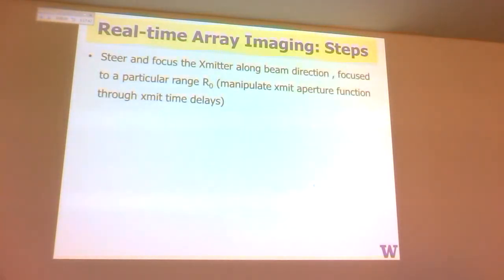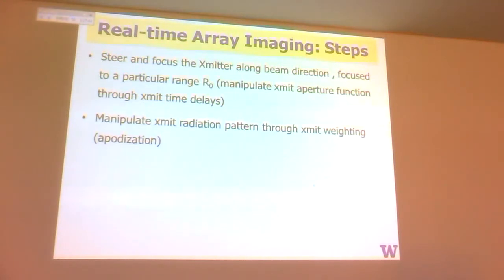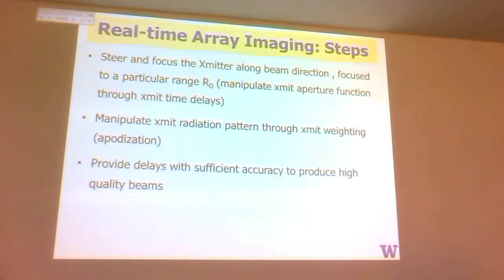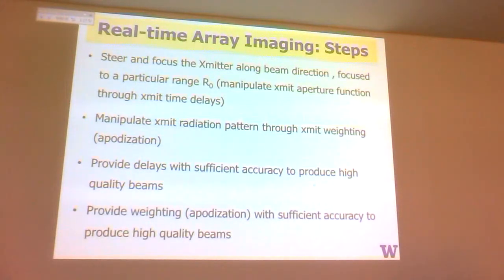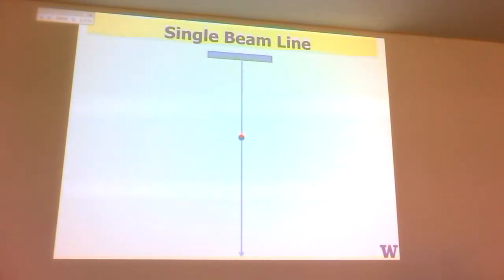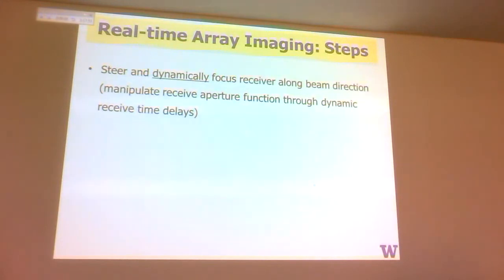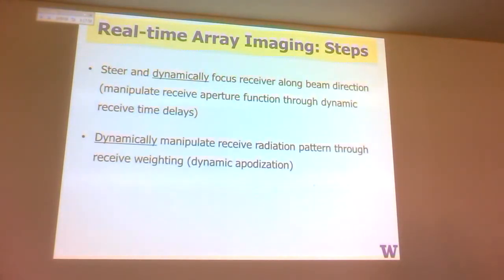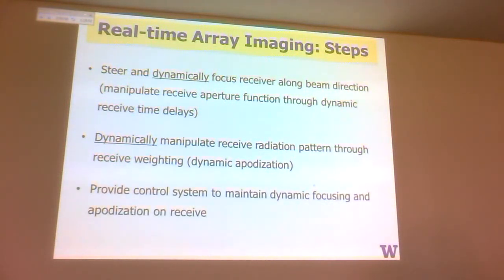So what are the steps? Steer and focus the transmitter, manipulate the transmit pattern to get what you want, provide delays to produce high quality beams. Then single beam imaging, again, boom, boom. You want to steer on receive, you want to steer and dynamically focus, as we've done. We want to weight this aperture to give you this constant numerical aperture, and you have to provide a control system that's doing all this in real time, okay?